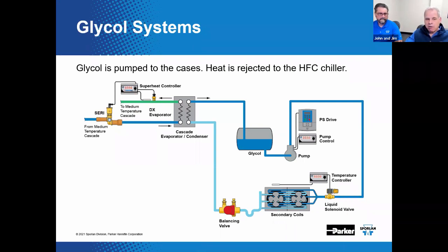But John, something happened here. Why didn't this keep going? Well, to put it succinctly, everybody finally realized that they can't quite outrun entropy. In other words, you have too many potential losses there. You have to run your chiller temperatures lower than what you would to chill the cases directly. Mm-hmm. And you have pumping losses. And the colder you get a glycol solution, the harder it is to pump. You can gain some efficiency back by going to higher glycol temperatures and higher glycol flow rates. But then what you gain there, you lose with pumping energy. Mm-hmm. And so from a functionality standpoint, it's really good. It works. It helped with the GWP issue. But from an energy standpoint, it's not good.